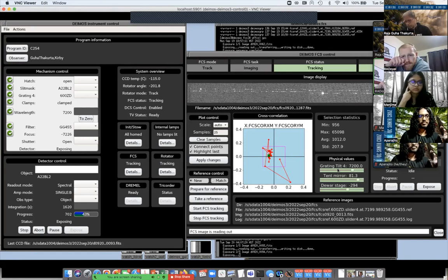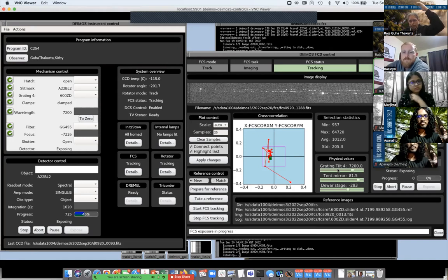For example, there have been nights when there's been such severe snowstorms on Maunakea that the crew that goes in to fill liquid nitrogen on a regular basis would not be able to get up to the summit, sometimes for a week. And so then the amount of liquid nitrogen in the dewar would boil off, and the detectors would start to warm up, and that's not good for the detectors. So now they have an autofill line where it detects that any dewar has low nitrogen, it autofills that. But even that can keep going only for a certain amount of time.